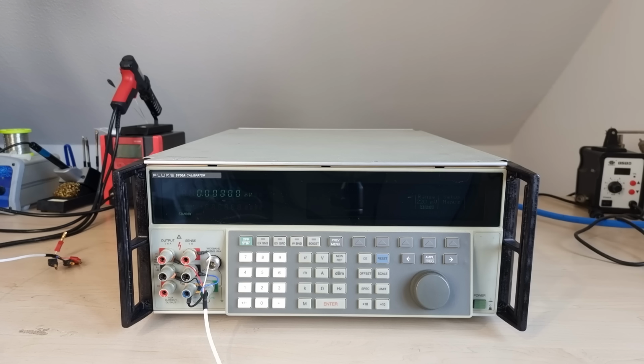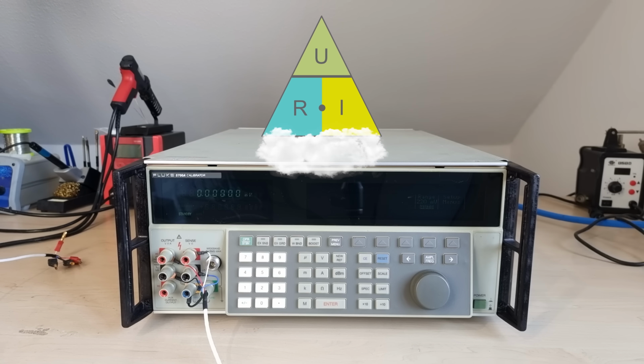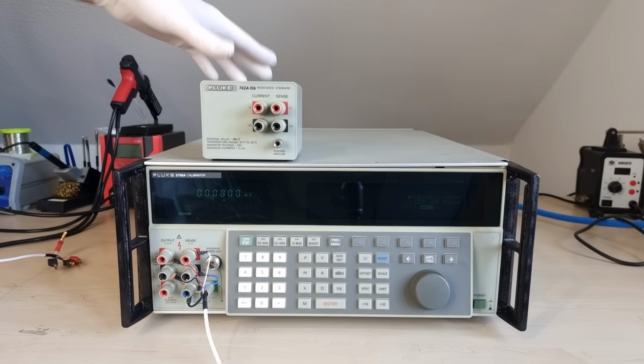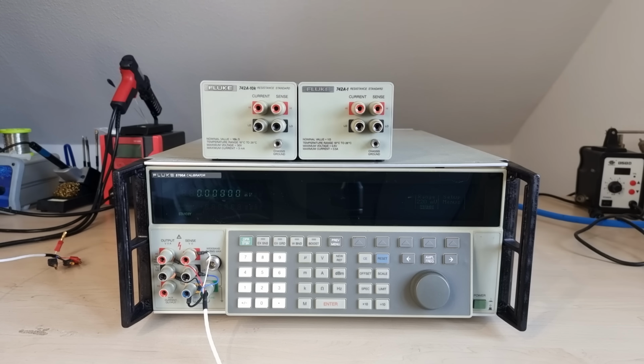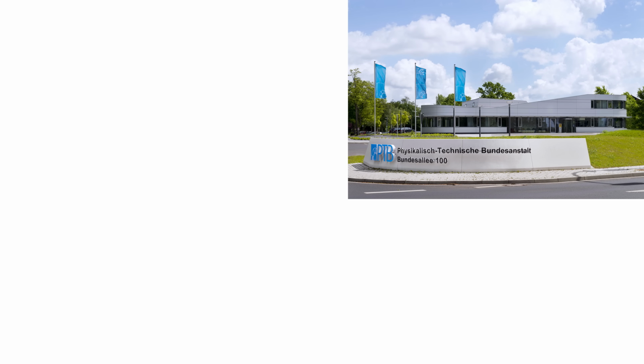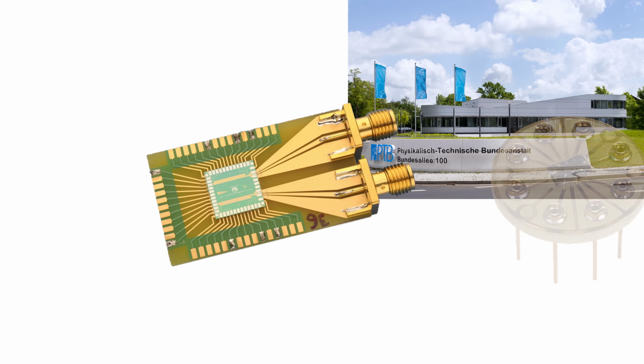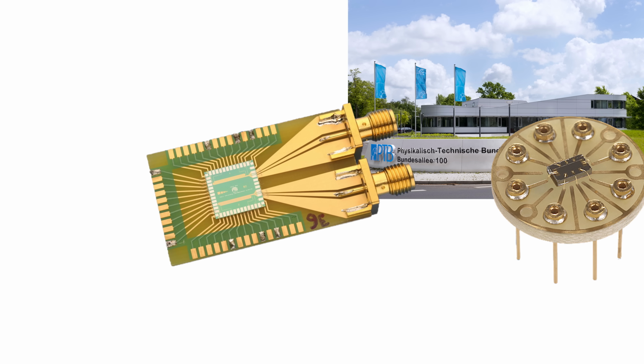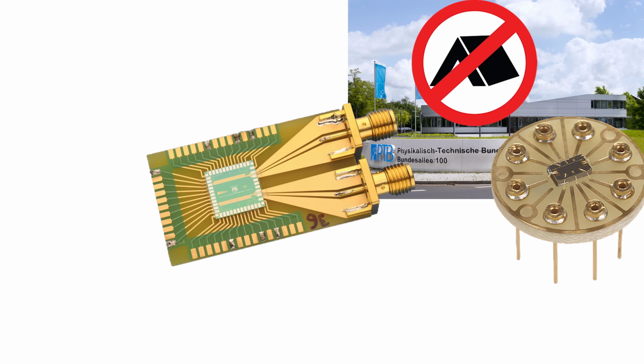Theoretically, it's not that difficult. The 5700 can combine its functions in various ways, allowing it to perform a full self-calibration of all 41 voltage, current and resistance ranges, using only 3 external standards. Fluke calls it artifact calibration, and it needs a 10 kilo ohm and a 1 ohm resistor, as well as a 10 volt source. Practically, we still depend on a calibration service provider, and only the biggest of those can afford high-performance primary standards, like a Josephson voltage standard and a Quantum Hall resistance standard. Those who can usually don't allow pilgrimage and camping on site.